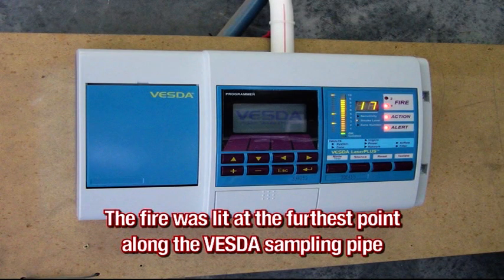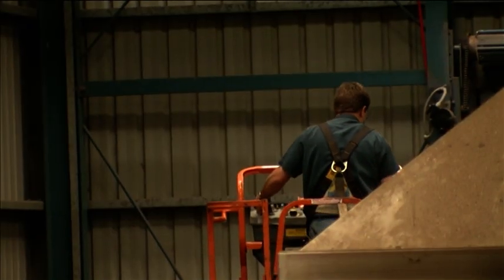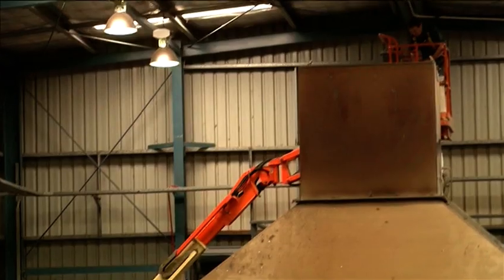The fire was lit at the furthest point along the VESDA sampling pipe, creating the worst case scenario for the VESDA system. Before conducting the tests, the detectors were checked to ensure they were 100% operational.